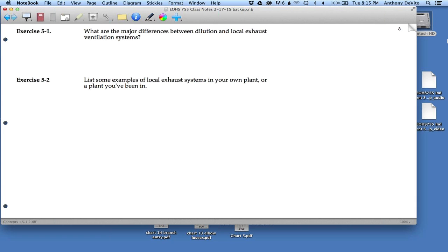That's a ventilation system. In fact, one of the students in a prior class was doing his project. I'm not really involved with students at the stage where they're getting ready to graduate into doing projects, but basically what used to be a thesis or a master's project, they call that a capstone or something like that nowadays, if I'm interpreting that correctly. And one student worked for the Department of Health, and it was his job to go around and inspect kitchen exhaust hoods in restaurants and food processing facilities. They have to be carefully inspected, and the fire department requires inspection, because as grease and other materials build up inside the hood itself and the exhaust system and the fan, that's a potential for a fire. In fact, a lot of serious fires get started because somebody hasn't maintained an exhaust system for a kitchen properly.